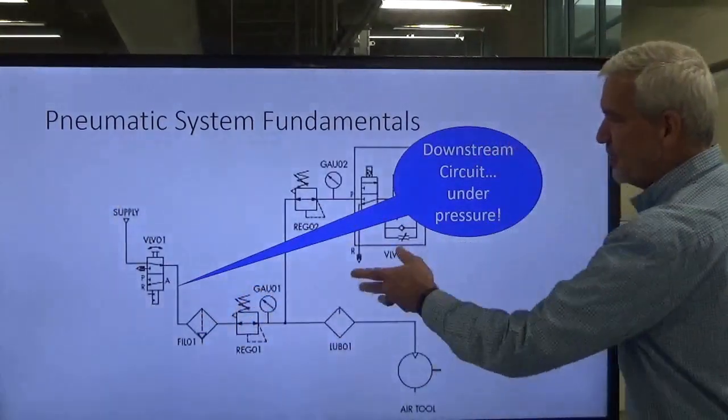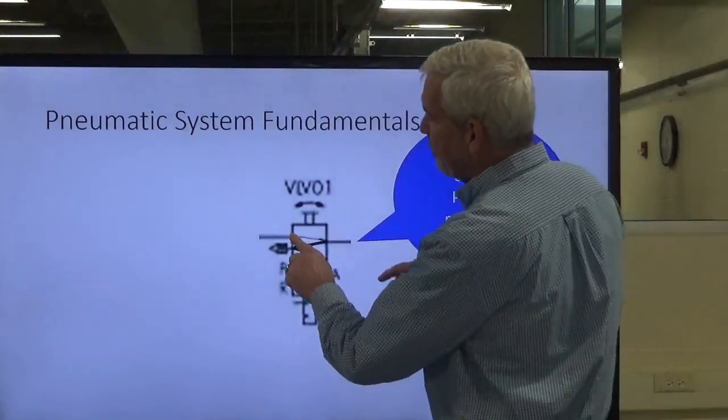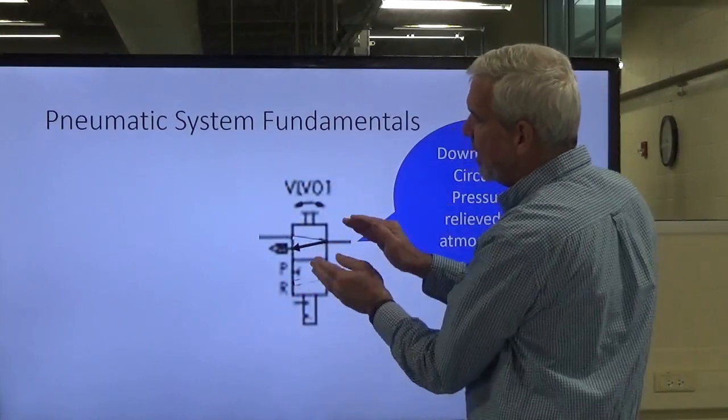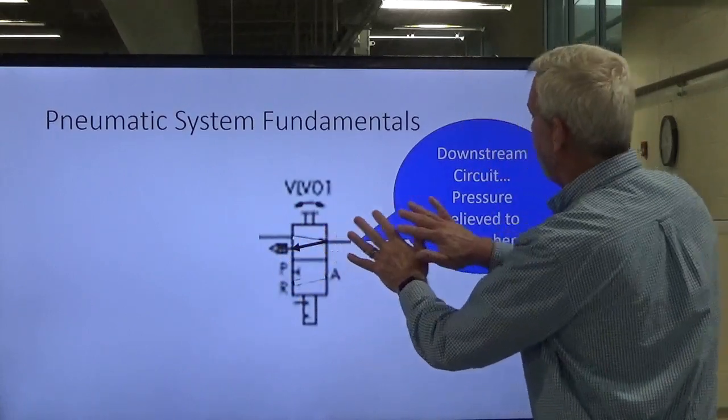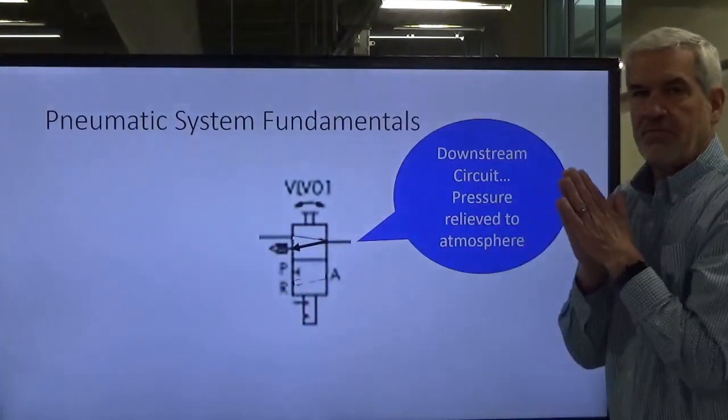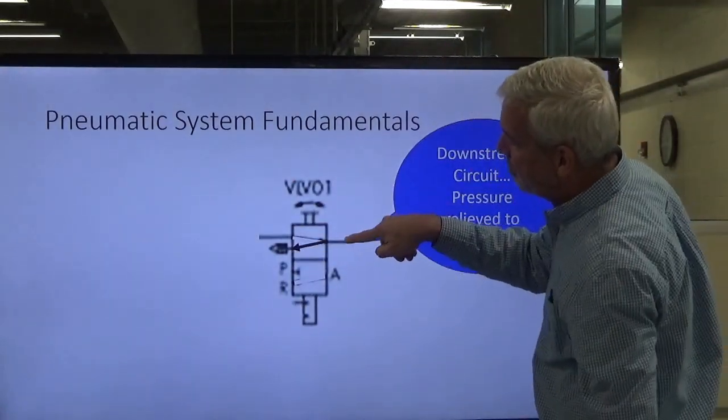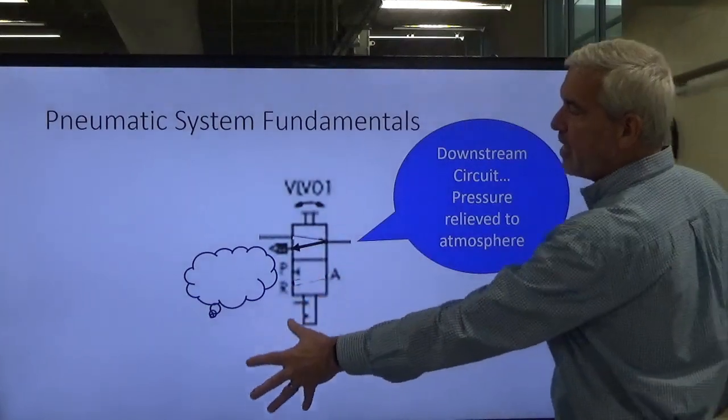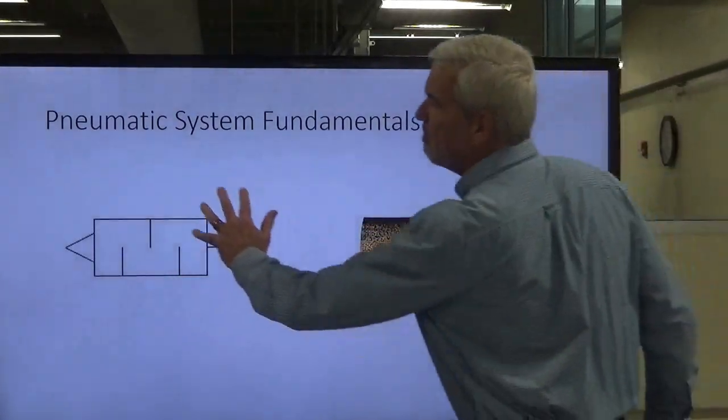When we shut off that valve, incoming air supply has no path because we've moved the spool. But we still have pressure in our downstream circuit. So when we shut off that valve, it creates a port for all the downstream pressure to come back out and exhaust into the atmosphere through a muffler.